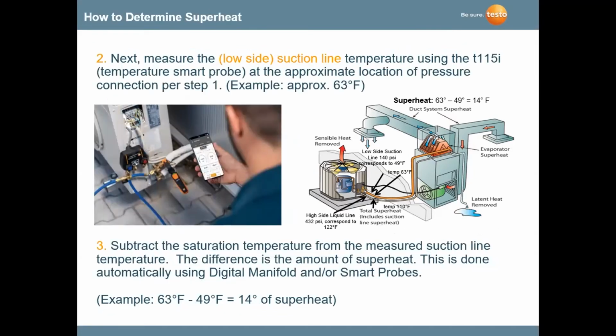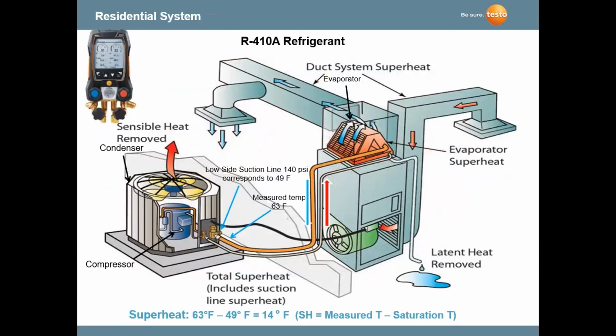Again, low side suction line temperature. We're using what we call wireless probes now. You don't have to worry about plug-in type temperature probes. In this case, it's on the suction line, and we're getting the temperature of the suction line through a wireless temperature probe. You can see here the service ports and where we would take the temperature measurement. Again, you're not using any type of math. All the calculations are done through a chip.